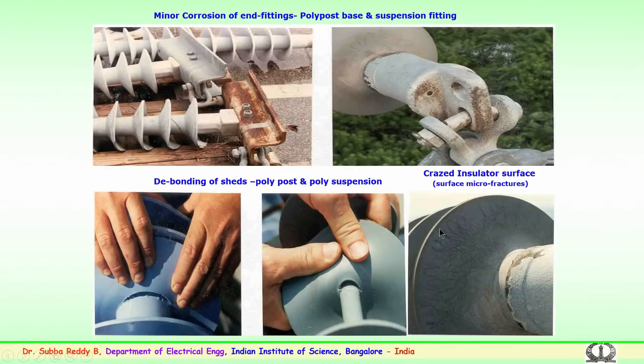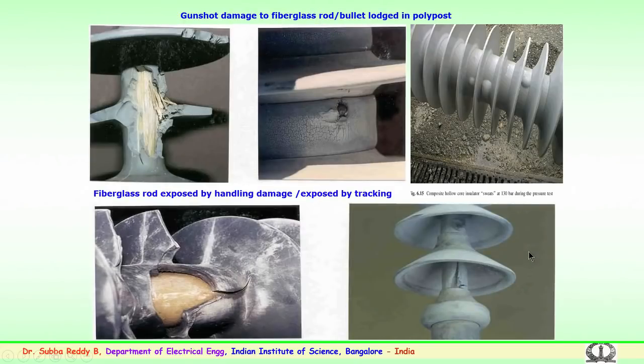So, special care has to be taken into consideration. There are failures in some of the countries due to gunshots, where failures have happened to the fiberglass rod or the post insulators, damaged by the bullets which are spread.